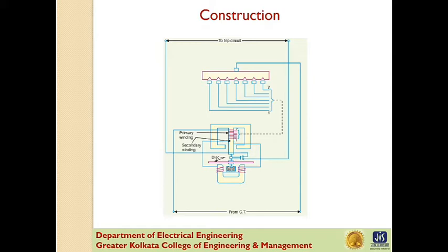The spindle of the disc carries the moving contact, which bridges with the fixed contacts when the disc rotates through a preset angle. This angle can be adjusted to any value between 0 degree to 360 degree. By adjusting this angle, the travel of the moving contact can be adjusted and hence the relay can be given any desired time setting.